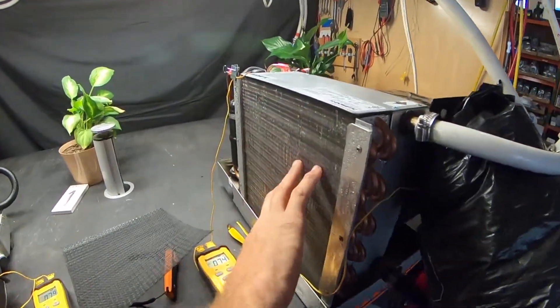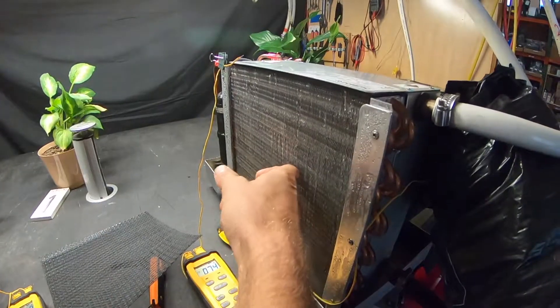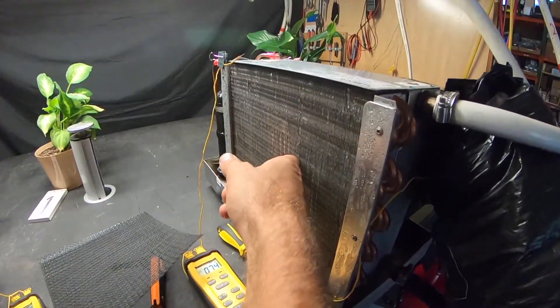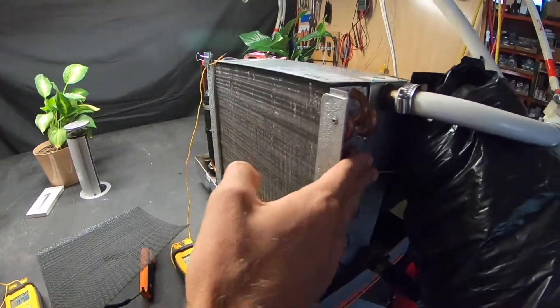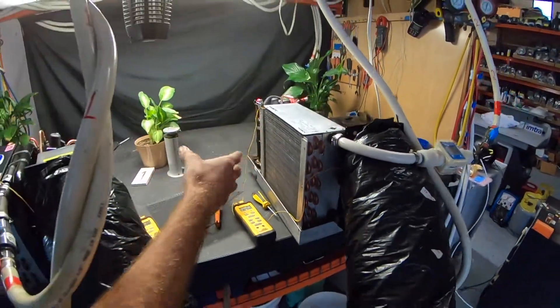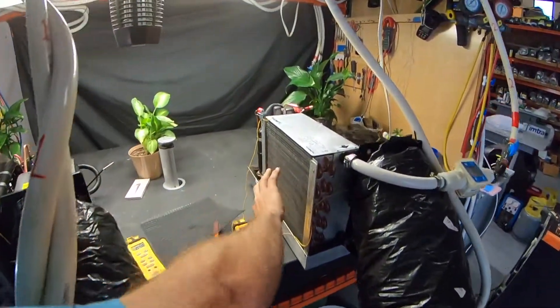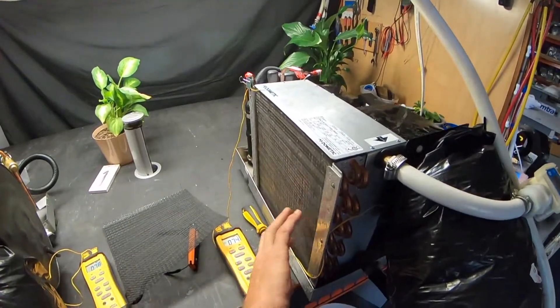You'll see over here, we're talking about an aluminum evaporator since it's bare aluminum, no coating, no nothing. So we have aluminum with copper, and over a few years what typically happens is that this aluminum tends to somewhat fall apart.